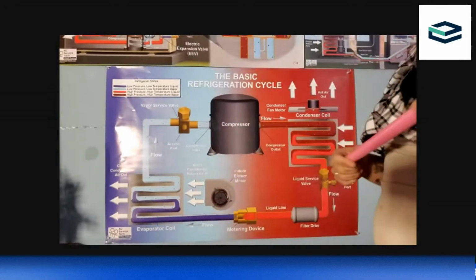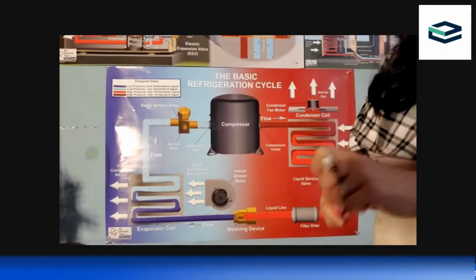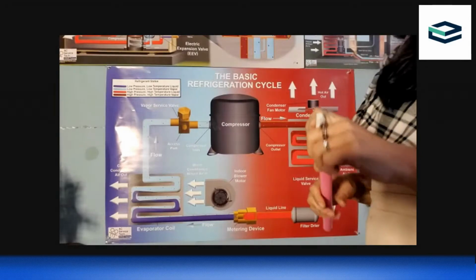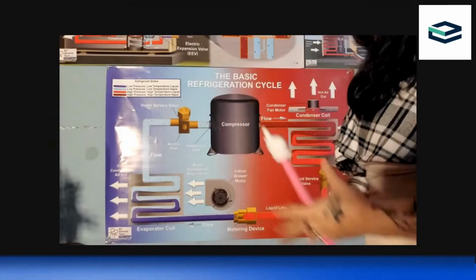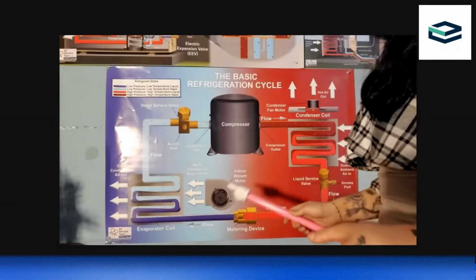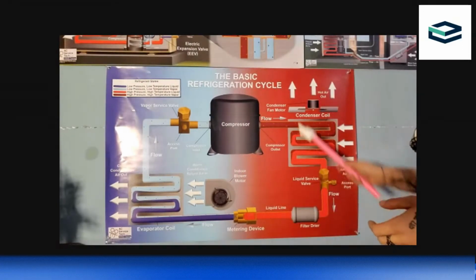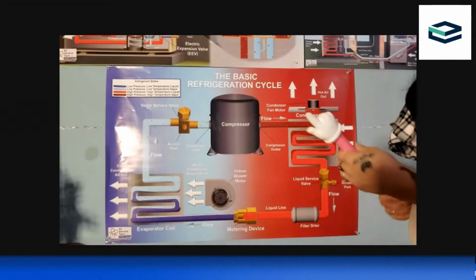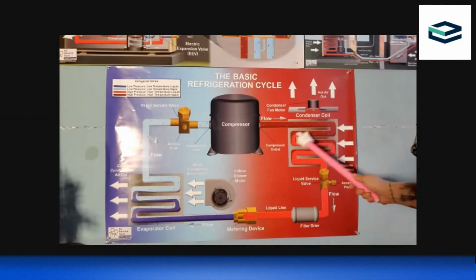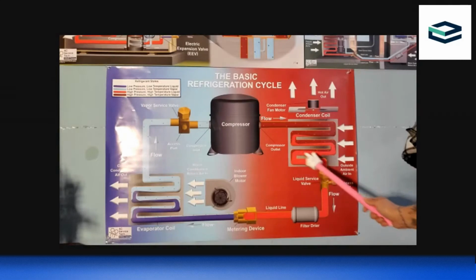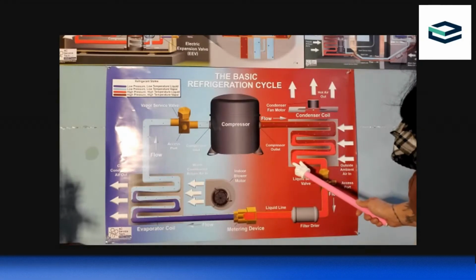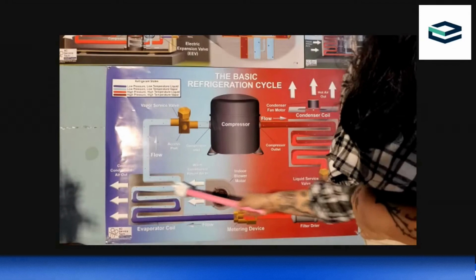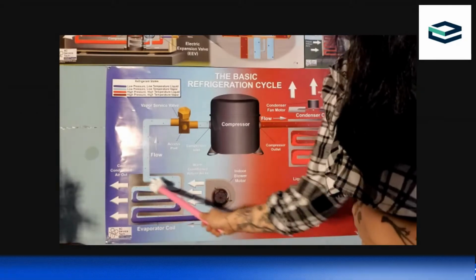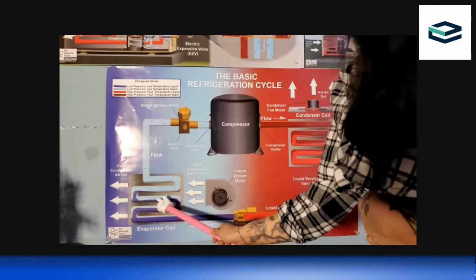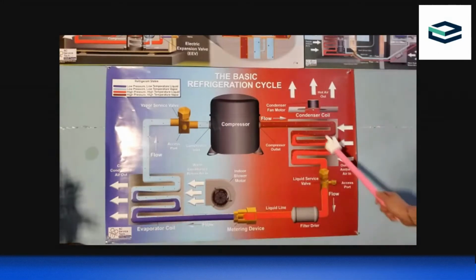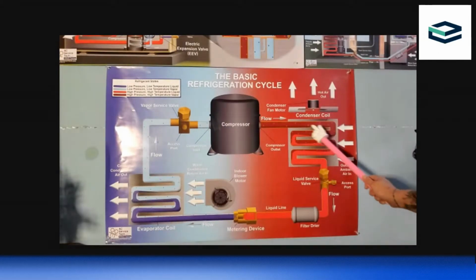So the first one that I want to start with is saturation temperatures. Saturation is when something is mostly a vapor or it's mostly a liquid. So when we come to these coils, right, we need to get a temperature that tells us at what temperature is it mostly liquid here in the condenser coil. And then on the other side, where is it mostly gas? So what temperature is this spot at where we're changing almost entirely from liquid to gas? And then this temperature here where we're changing almost entirely from gas to liquid.